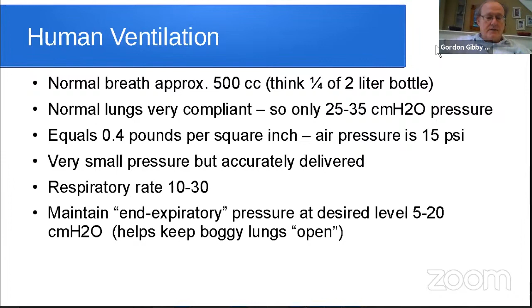This is 0.4 pounds per square inch. It has to be very accurately delivered. The respiratory rate has to be in the range of 10 to 30 in order to have optimal transfer of power. You can think of that as SWR matching. And we want to maintain an end expiratory pressure at a level chosen between 5 and 20 centimeters of water, and that's designed to keep boggy lungs open.